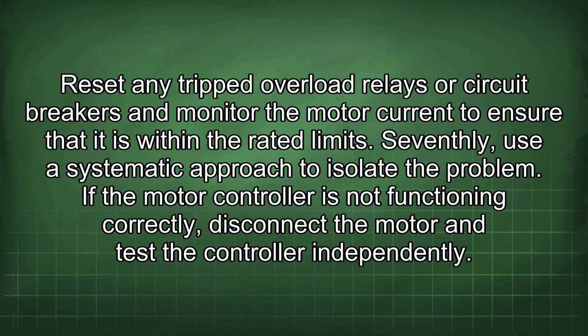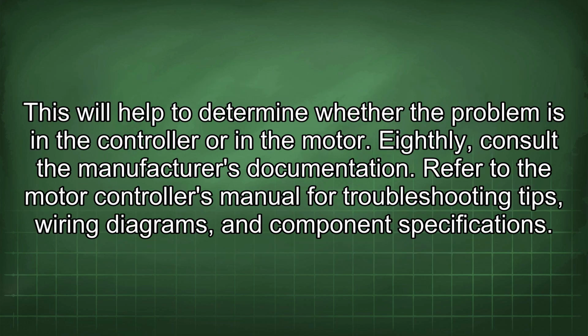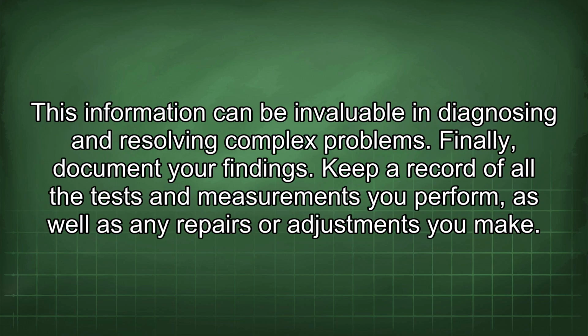Seventhly, use a systematic approach to isolate the problem. If the motor controller is not functioning correctly, disconnect the motor and test the controller independently. This will help to determine whether the problem is in the controller or in the motor. Eighthly, consult the manufacturer's documentation. Refer to the motor controller's manual for troubleshooting tips, wiring diagrams, and component specifications. This information can be invaluable in diagnosing and resolving complex problems.